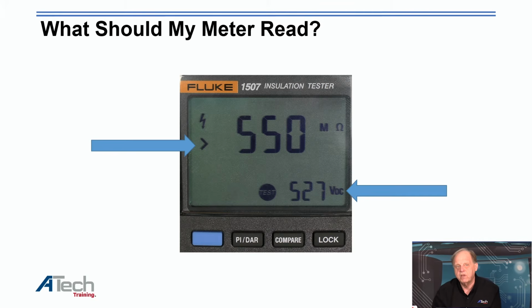Your meter should read 550 megohms or higher. That indicates the resistance is beyond the range of the meter. If you look on the left-hand side, there's a little squiggle, which means you're being tested right now. The voltage outputted at this point was 527 volts.